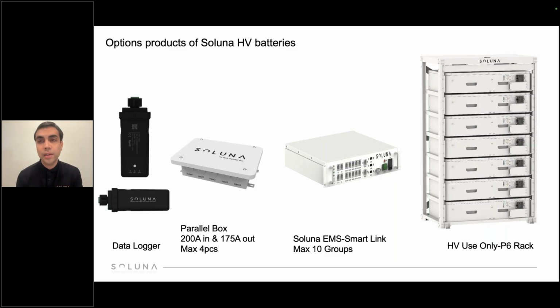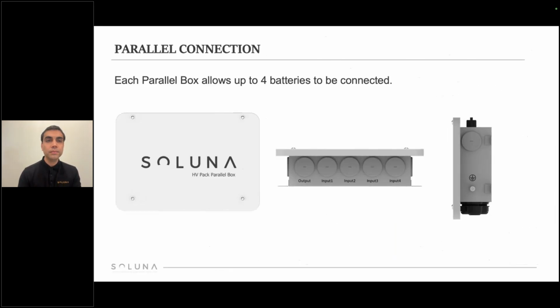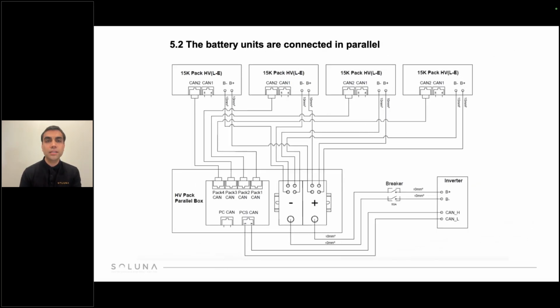We have the Soluna high voltage-only P6 rack, so you have the ability to stack up to 6 rack batteries in the one rack. Soluna EMS Smart Link, where you can connect up to 10 groups, and the parallel box that is for 200 amps in and 175 amps out, and data logger. So this is one of the examples, and when it comes to the connection in parallel of our 15K, coming into the parallel box, going to the breaker and into the inverter. So you can see one inverter able to communicate with 4 batteries.